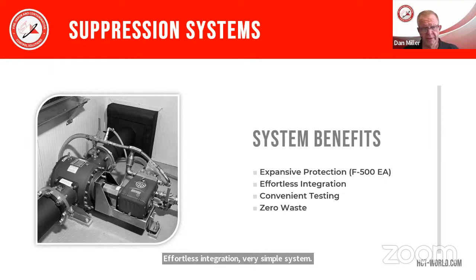So when you test this, you don't have to expel agent on the ground, for example, and cause a cleanup problem or a disposal problem. You can simply turn a valve and the agent goes back into the concentrate tank as you're expelling water out, but it tests both sides of the system, the water motor and the concentrate pump. The concentrate's just put back into the tank rather than put into the stream during a test mode. So there's zero waste. There's a lot of benefits to this system, and one of them is just the wide-ranging volume that's available.